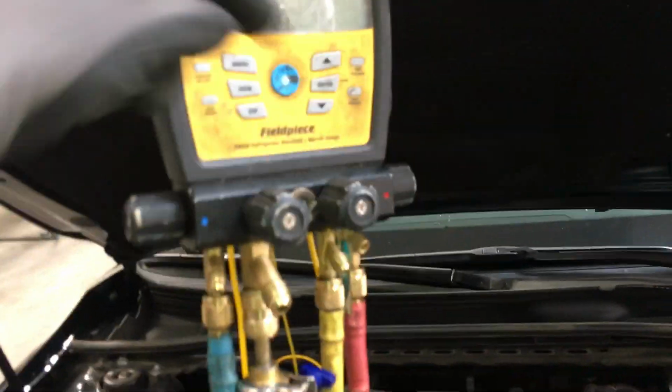I have the high side off. Turn this one on, I have this on. We're at 60 microns at this point from this sensor in this manifold. Now let's open up this port going to that sensor. And by the way, let's go one step further because I did open this just for you guys.